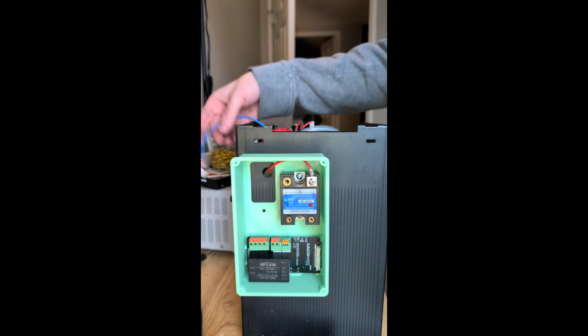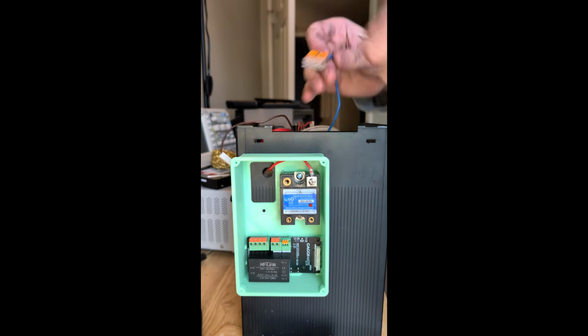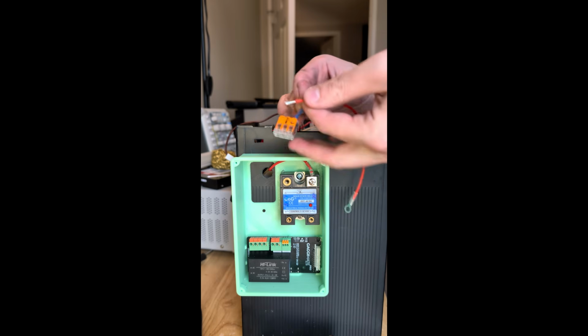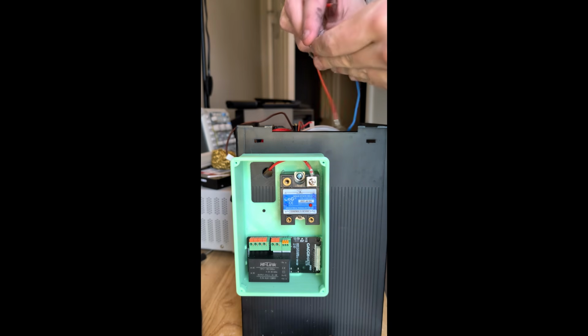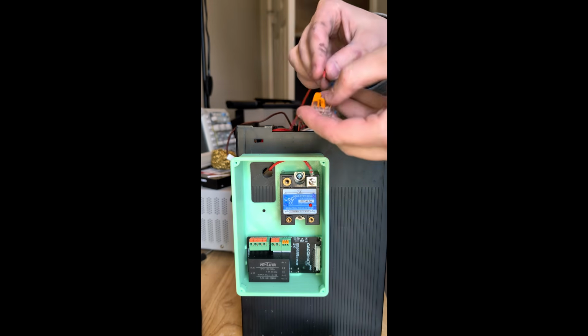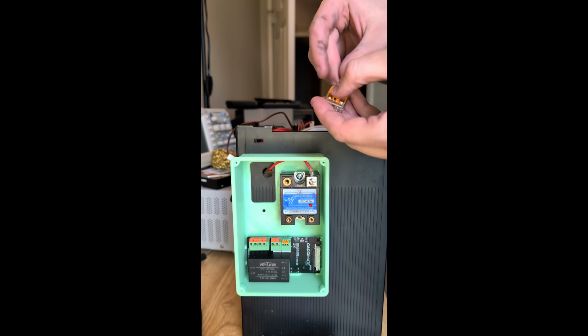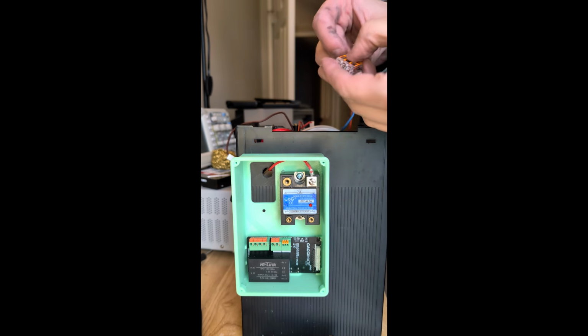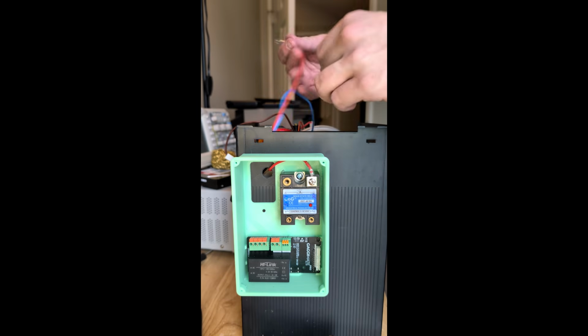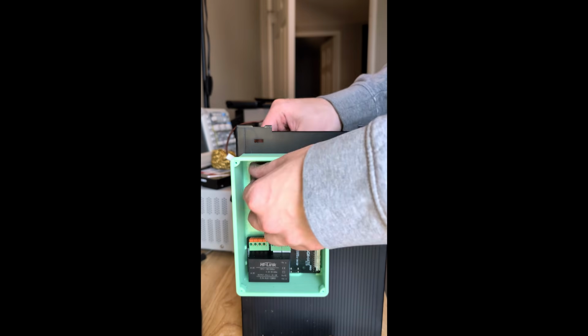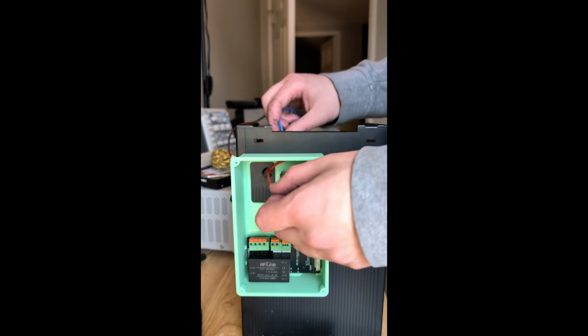The other side of the SSR needs to be connected to live. So create a short wire that's going to go from the live Wago that we previously set up. And again, fish this wire through the hole and crimp a hoop or hook connector on the other end and screw it into the other hole on the SSR.